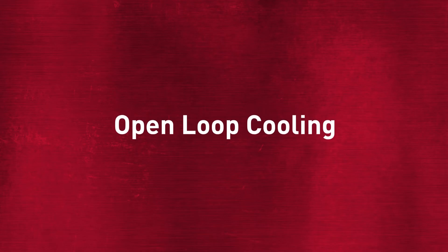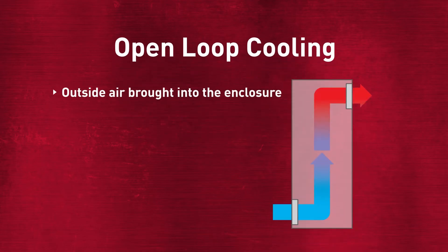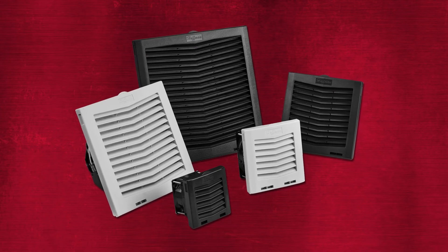Open-loop solutions will always have our temperature above the ambient temperature — this is something that people need to pay attention to. Anytime you bring outside air into the enclosure, it's open-loop cooling, whether that be by louvers, fans, or filtered fans.